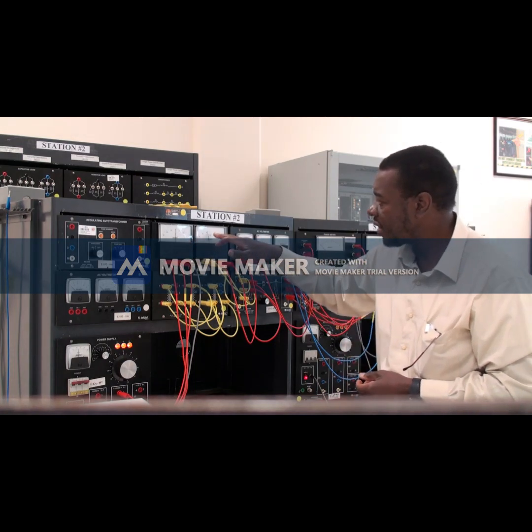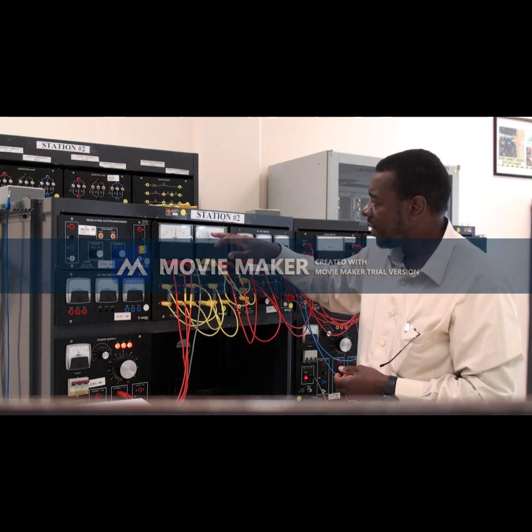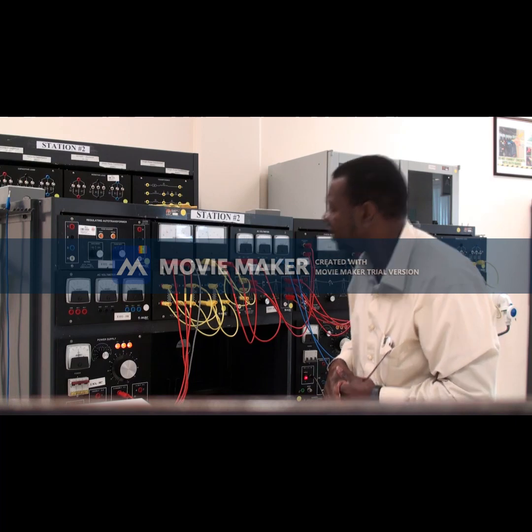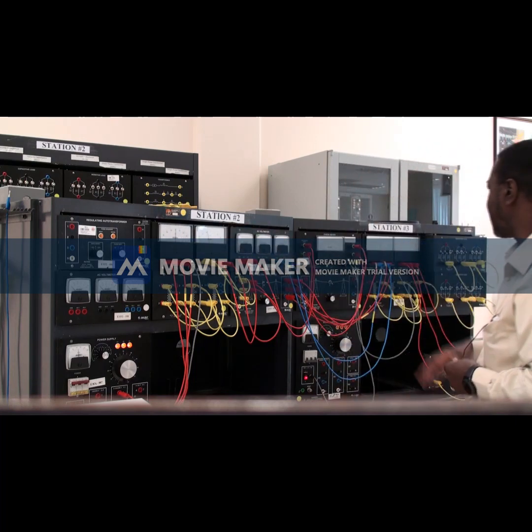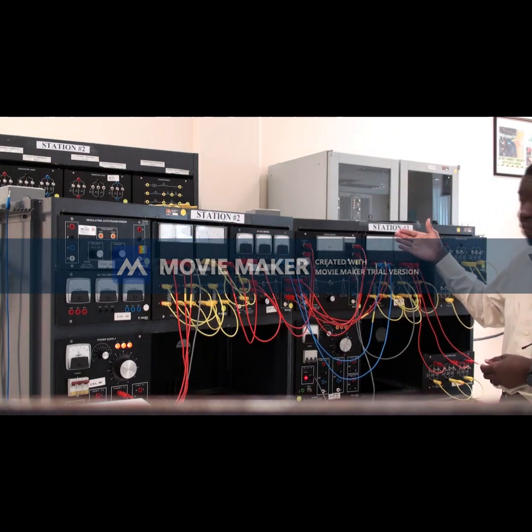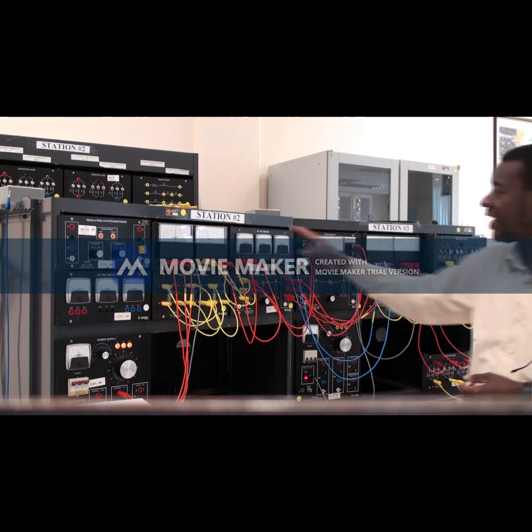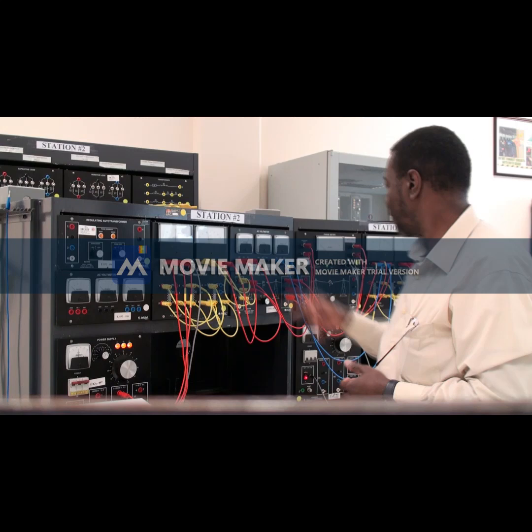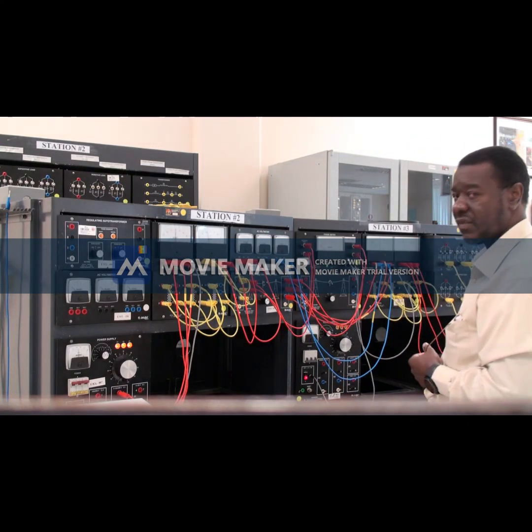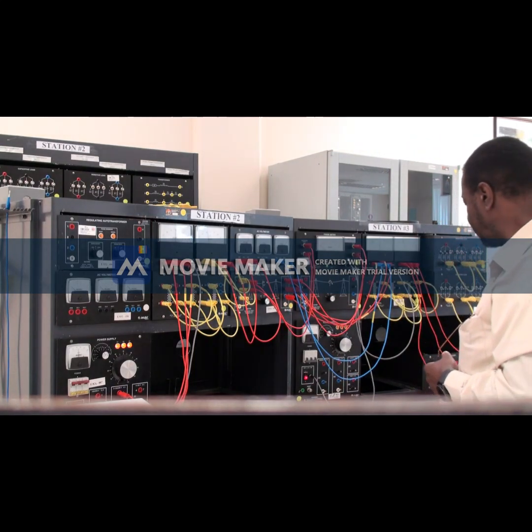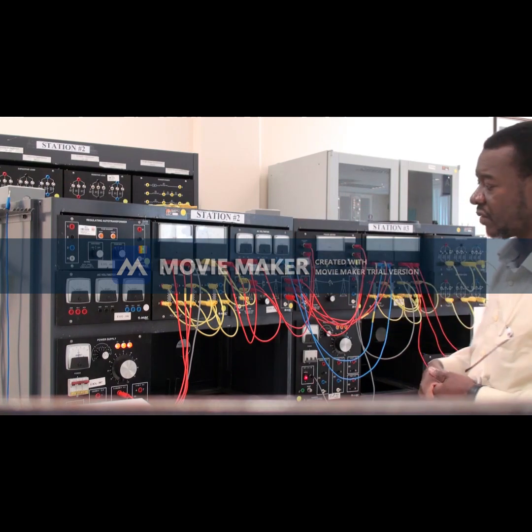We have about how much here? About 85 VAR. Here we have also 0 watts. And we can see here a negative reactive power, which means that the power is going from the receiver to the system, or to the supply.